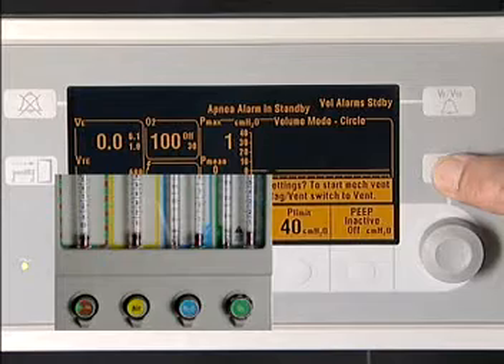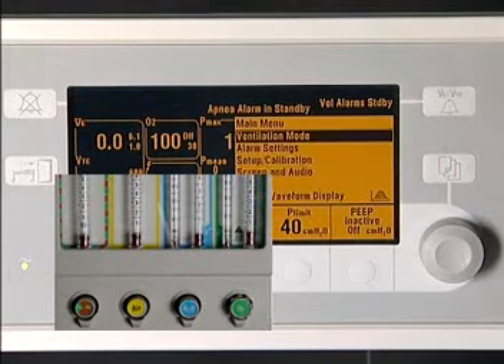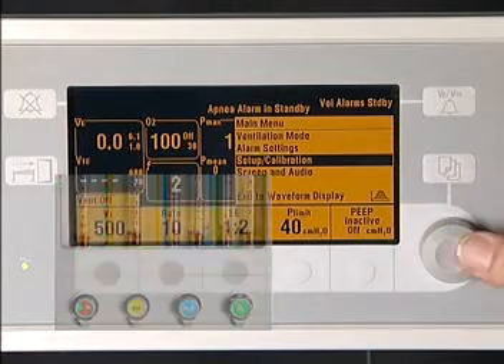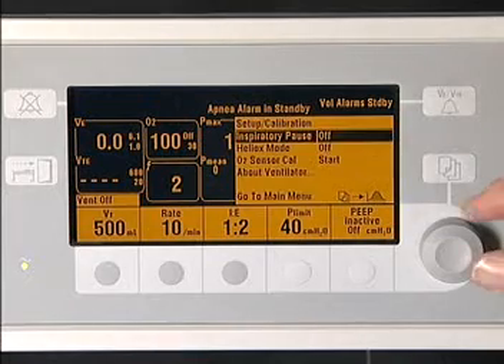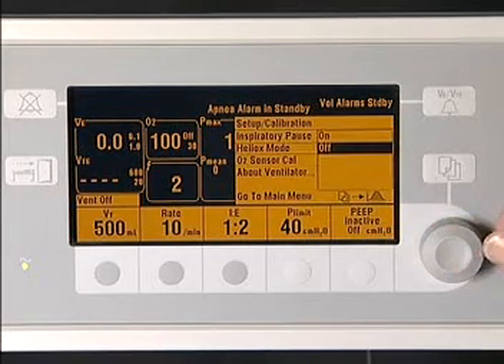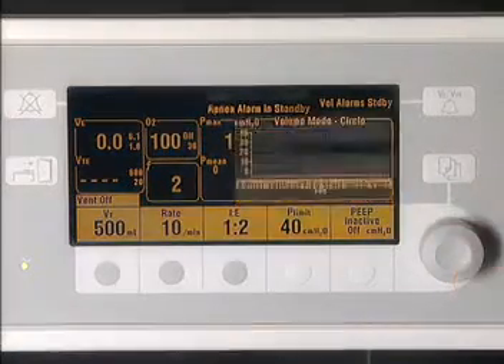The Aestiva is available with a helium-oxygen mixture. If the option is present and utilized, the operator should navigate to Heliox mode in the ventilator setup menu to assure the volume monitor recognizes the change in gas density.